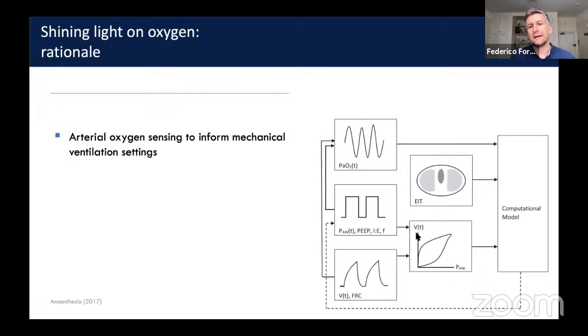For example, the monitoring of the tidal volume, the volume of air that is delivered per breath, and the pressure in the airways. All this information, together with this arterial oxygen signal, could be used by a computational model to determine, as illustrated by the dashed line, the settings of the mechanical ventilator. For example, the pressures that are necessary for ventilating a given individual patient, or the respiratory frequency, how many breaths we could give per minute.